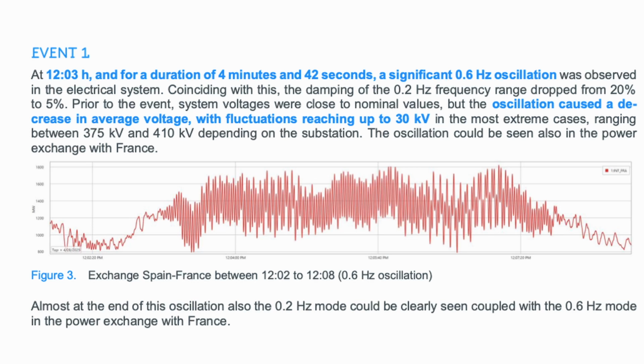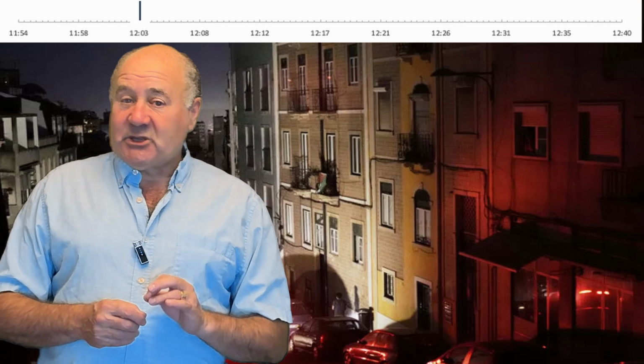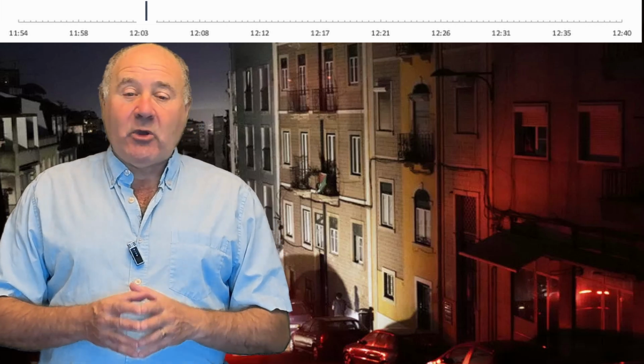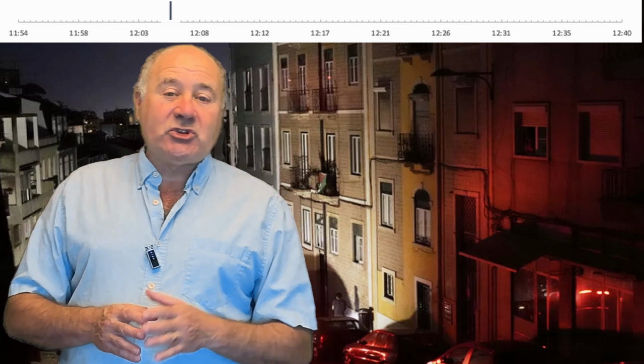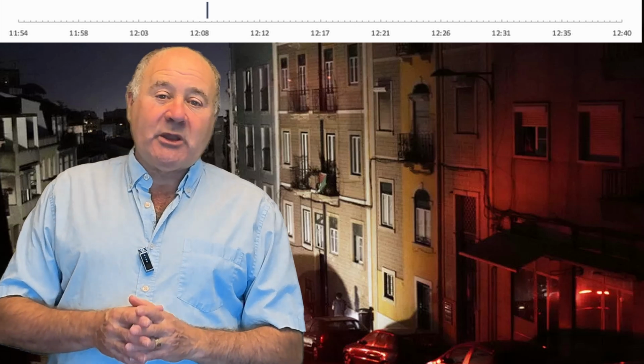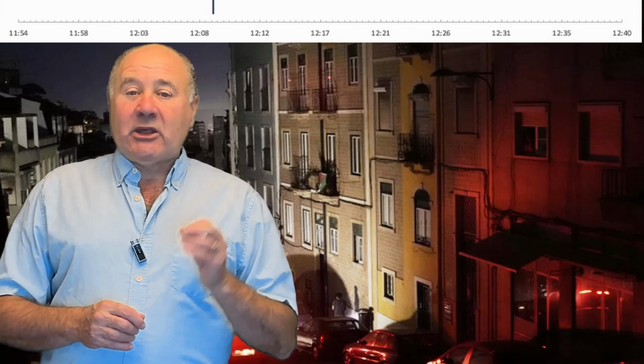For a duration of 4 minutes and 42 seconds, a significant 0.6 Hertz oscillation was observed in the electrical system. The grid operators reduced power exported to France and Portugal and made other changes to damp down these oscillations. The source of these oscillations was eventually determined to be a solar plant in Badajoz.